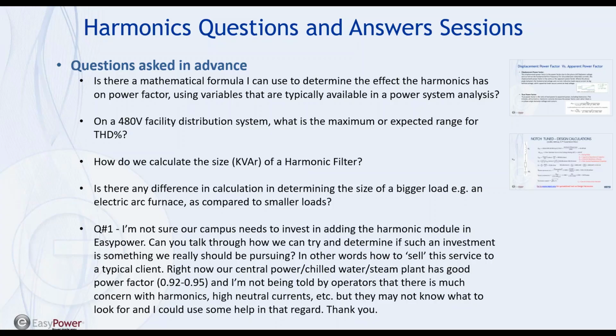Okay, so I will read this next one. This person had two questions. Question number one says, I'm not sure our campus needs to invest in adding the harmonic module in EasyPower. Can you talk through how we can try to determine if such an investment is something we should be pursuing? In other words, how to sell this service to a typical client. Right now, our central power, chilled water and steam plant has good power factor, between 0.92 and 0.95. And I'm not being told by operators that there's much concern with harmonics or high current, but they may not know what to look for, and I could use some help in this regard.